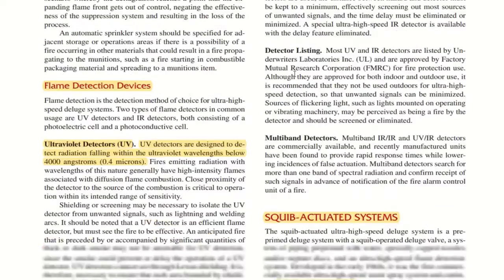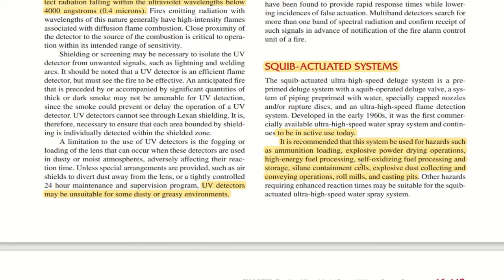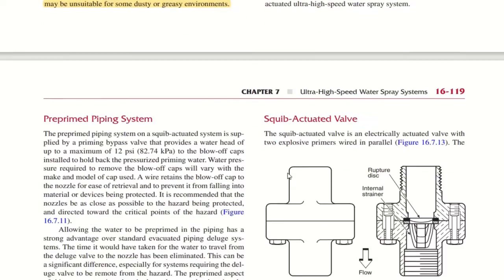Apart from that, you have squib actuated systems. It is recommended that this system be used for hazards such as ammunition loading, explosive powder drying operations, high energy fuel processing, self oxidizing fuel processing and storage, silane containment cells, explosive dust collecting and conveying operations, roll mills and casting pits. UV detectors may be unsuitable for some dusty or greasy environments. So the highlighted points are very important.